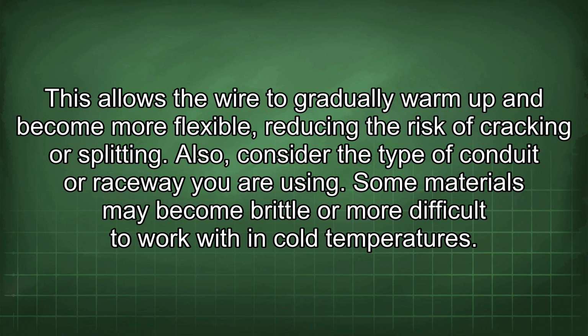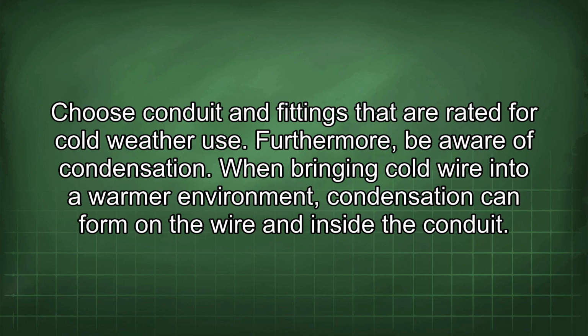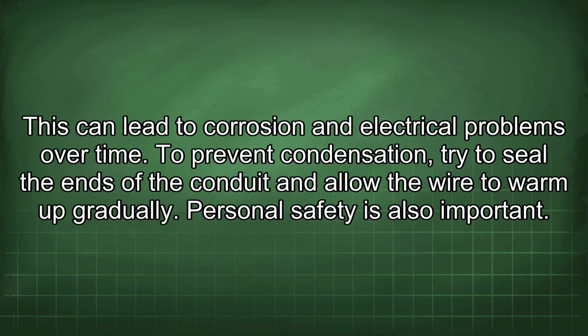Also, consider the type of conduit or raceway you are using. Some materials may become brittle or more difficult to work with in cold temperatures. Choose conduit and fittings that are rated for cold weather use. Furthermore, be aware of condensation. When bringing cold wire into a warmer environment, condensation can form on the wire and inside the conduit. This can lead to corrosion and electrical problems over time. To prevent condensation, try to seal the ends of the conduit and allow the wire to warm up gradually.